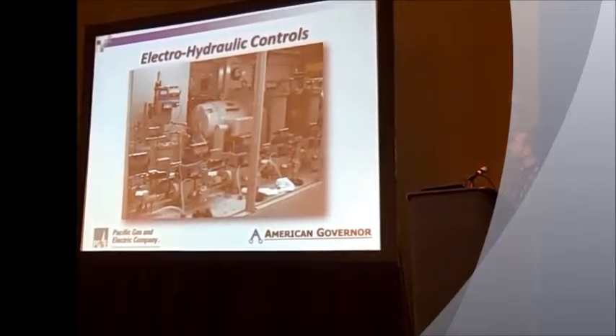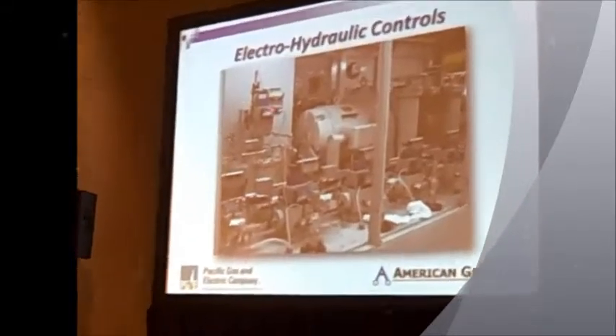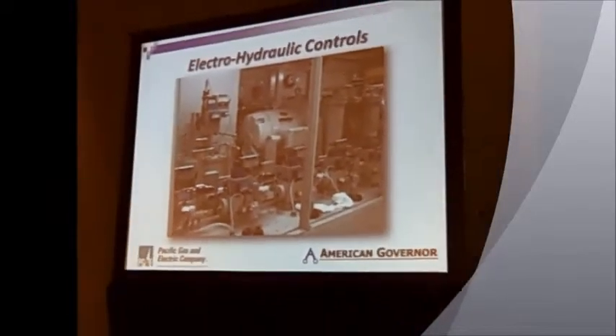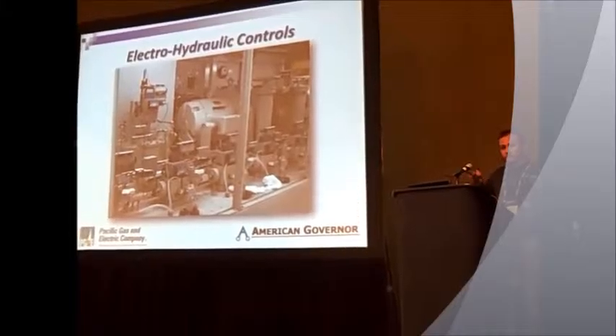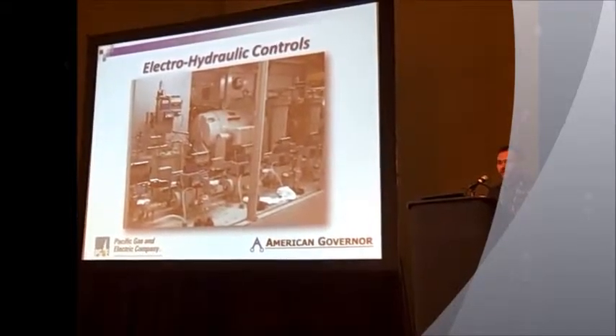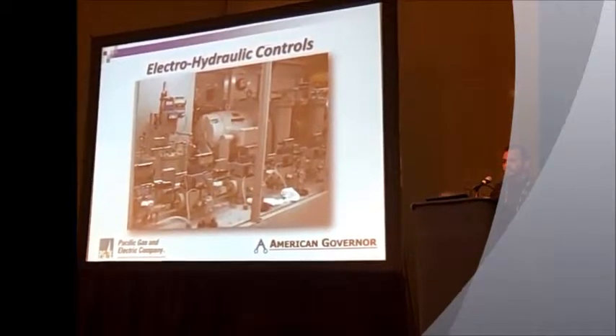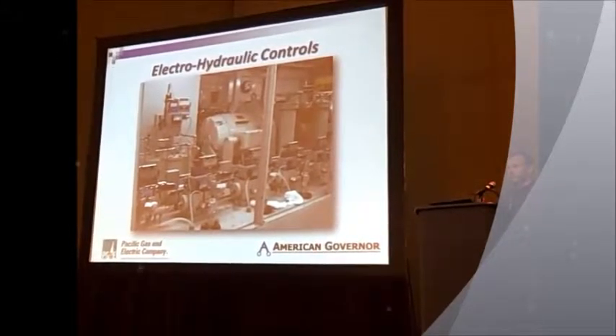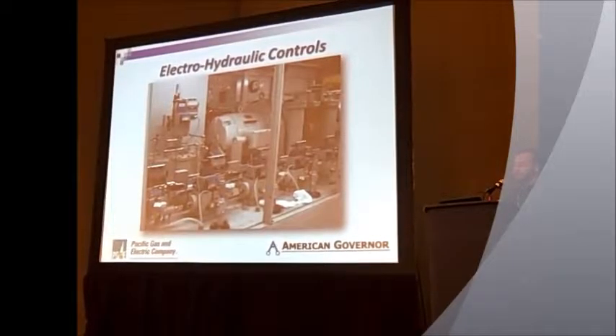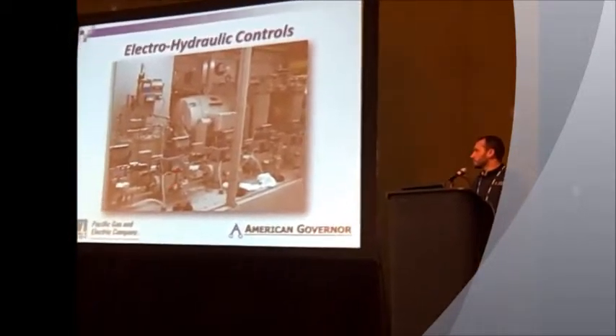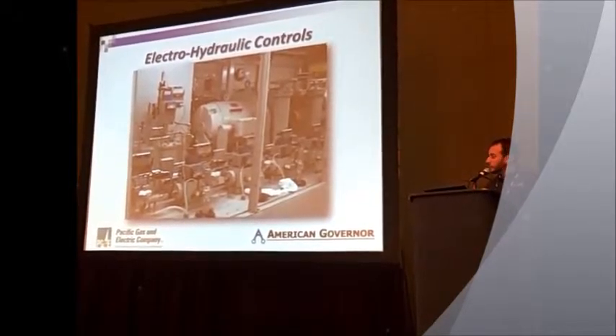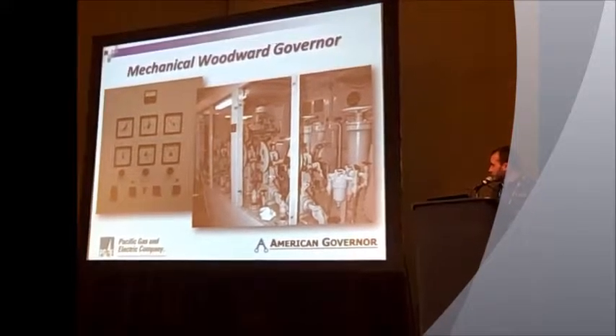This is the inside of the hydraulic control cabinet. You have your deflector controls using modern Bosch proportional valves with LVDT feedback, and a very similar configuration on each of the 6 needles. This right here is where the vast majority of the gains in converting to a digital governor are, especially on a unit like this, where before the governor was controlling the deflectors, which was then controlling the master needle, which was then controlling the 5 slave needles. A lot of slop between those several steps resulted in poor needle control, which resulted in poor megawatt control and poor ability to transition between needles. We can now individually control each needle very precisely, and that's really where all the gains are. And just to give you a comparison, this is again what the old system looked like. So you can see how much simpler, cleaner, and more direct the control is.